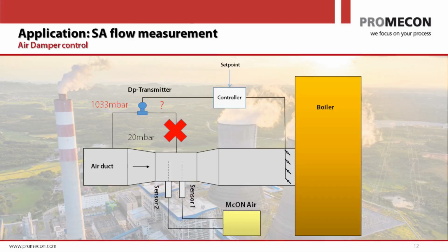If one leg is blocked, what will happen is that one leg, the free one, sits on 1033 millibar plus the static pressure, and the other leg is undefined. So you will not see your typical 20 millibar or your few inches of water gauge in delta pressure. You will see a different pressure which depends on changes of barometric pressure outside your plant. You can see 20 millibar of pressure is not very much as compared to 1,000 millibar. Yeah? We're talking about 2%. So if you have, for example, a thunderstorm coming and your barometric pressure goes down from 1,033 millibar to 1,000 millibar, all of a sudden your full scale delta pressure is already used up.